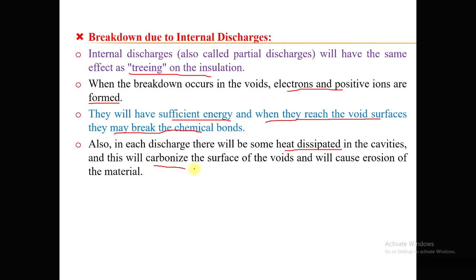This will produce channels and pits on the cavity surface and increase the electrical conduction, which further leads to chemical degradation, resulting in active discharge products formed during the breakdown of the cavity. All these effects act simultaneously and result in gradual erosion of the material and consequently reduce the thickness of the insulation, which leads to breakdown. Here I can show you how it happens. This is the solid dielectric with void. Initially this is the thickness.